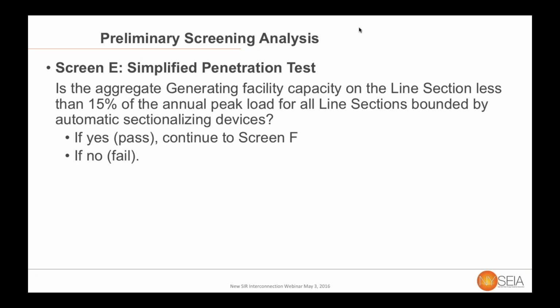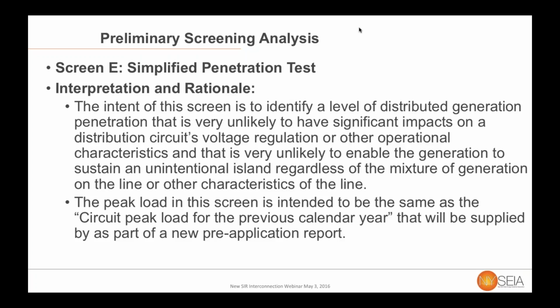So this screen is intended to be a sort of catch-all screen. If you are below 15% of peak load, it is taken that you will have very little likelihood of creating significant voltage, quality, or regulation impacts. The risk of unintentional islanding is not a concern. If you are below this 15% of peak load, all of the fault coordination issues, these are generally considered to be not a concern, and therefore you can interconnect without a full study.